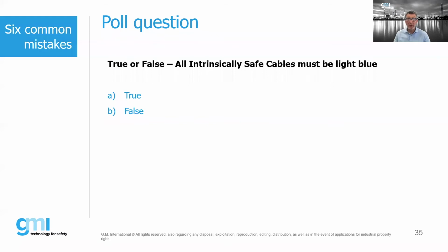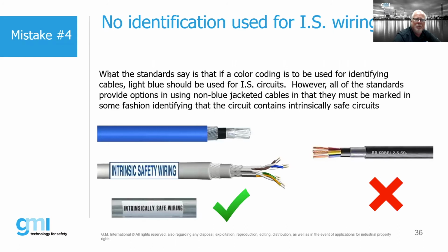So Bob, is it true or not true? It's not true. However, there are many clients out there that say their intrinsically safe wiring must be light blue. What the standard actually says is that it can be light blue. Generally speaking, all of the international standards and the US requirements are pretty much: if we're going to use a color coding to identify our cables, then light blue should be used for IS circuits.